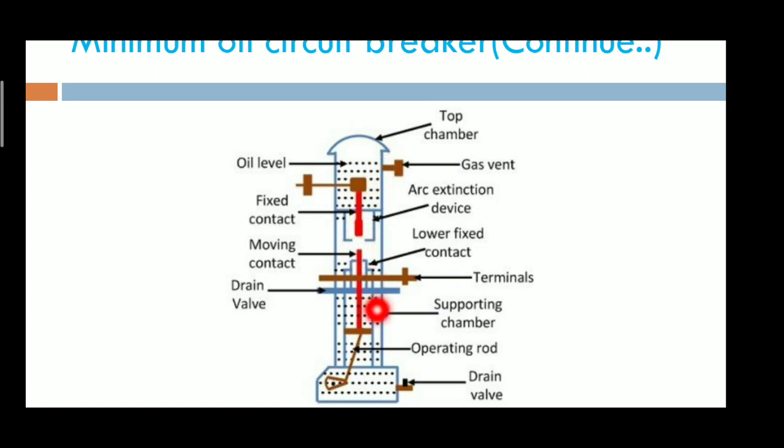Constructionally, the low oil circuit breakers are divided into 3 chambers. At the top of that we are using air as a cushion.